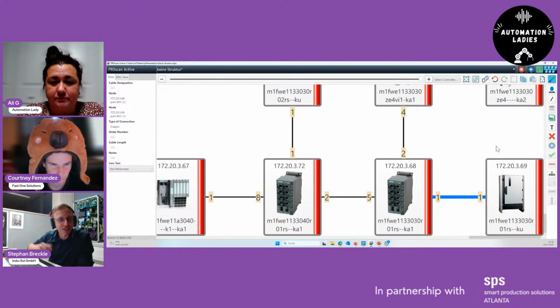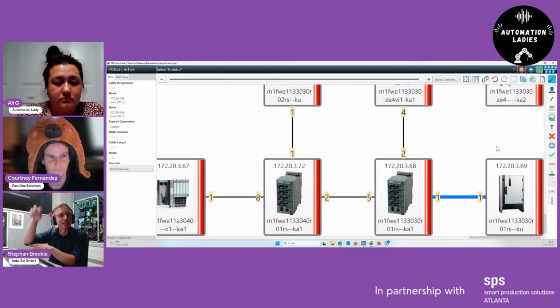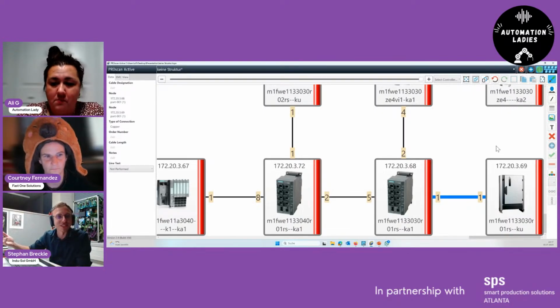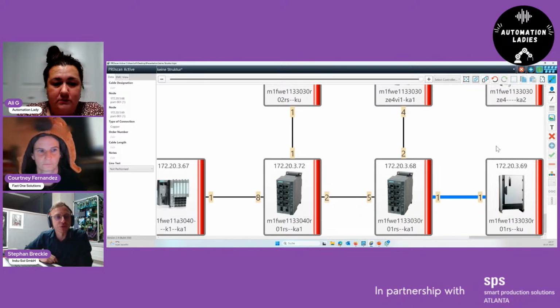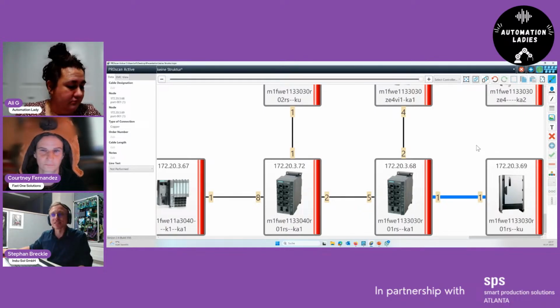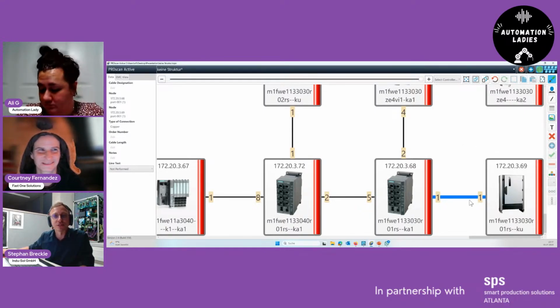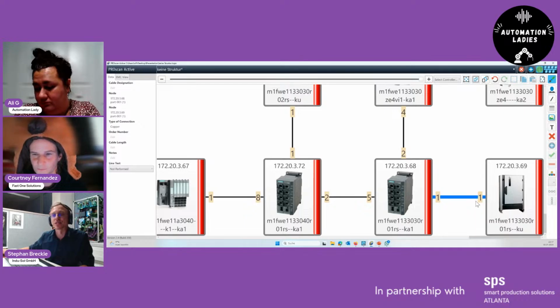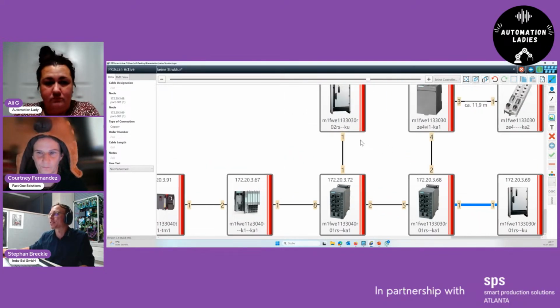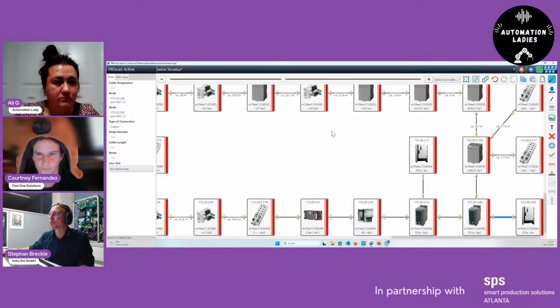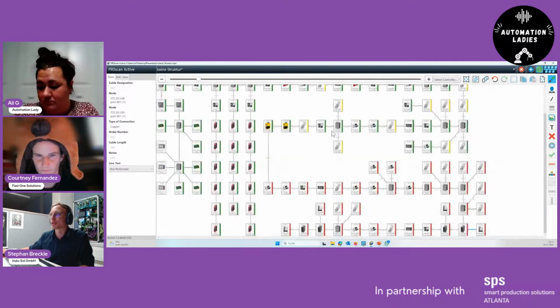The reasons are simple. It could be the cable because of the movement, or it's because of EMI, since each robot has an inverter inside that generates some current that runs through your system. This was the problem here as well - it was just an EMI issue because of the wrong motor cable.